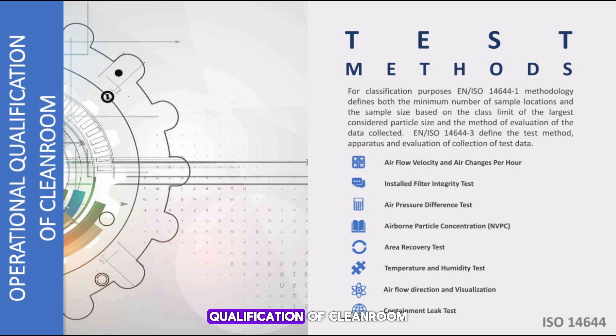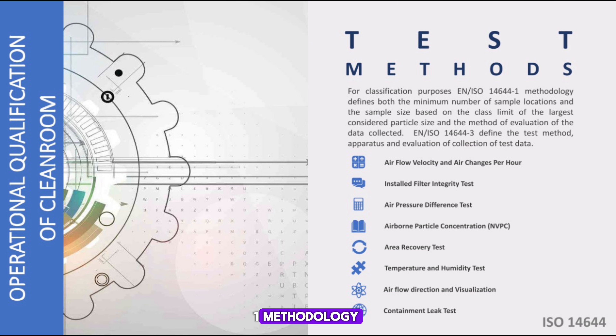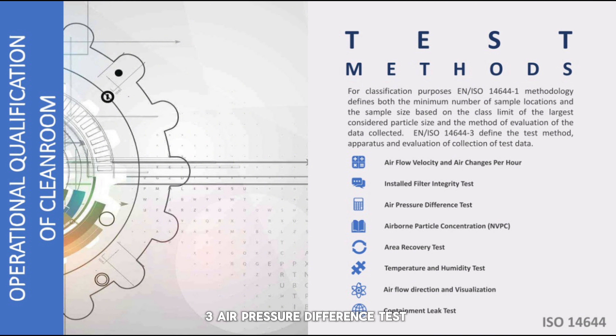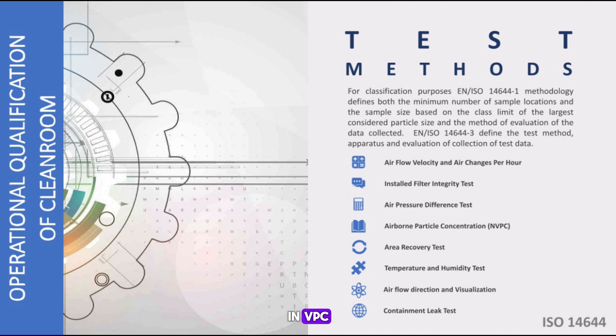Test methods for operational qualification of a clean room follow EN/ISO 14644-1 methodology for classification, which defines minimum sample locations and sample size. EN/ISO 14644-3 defines the test method, apparatus and evaluation. Tests include: airflow velocity and air changes per hour, installed filter integrity test, air pressure difference test, airborne particle concentration (NVPC), area recovery test, temperature and humidity test, airflow direction and visualization, and containment leak test.